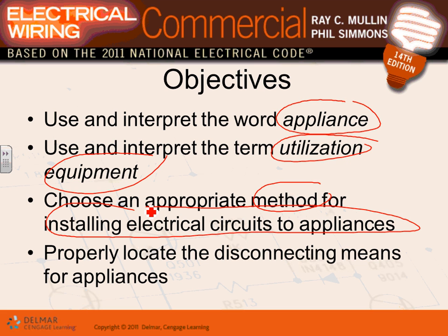Let me summarize what we do, guys. As electrical designers and electricians, people come to us every time there's a machine, any type of machine, an appliance, a fan, what not. They come to us to design a system for it. And you know what we do? We do three things, really, in the whole building, and they pay us to do that. We design a service entrance conductor to a building, power coming in with all the conductors and what not. Then we do feeders to go from panel to panel. And then from the last panel, we go branch circuit to feed this equipment, be it lights, be it receptacles, be it air handling units and what not.